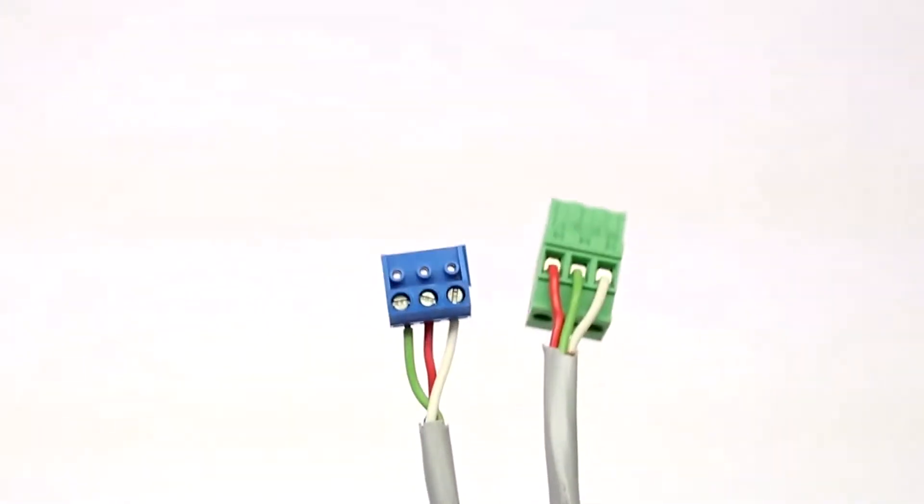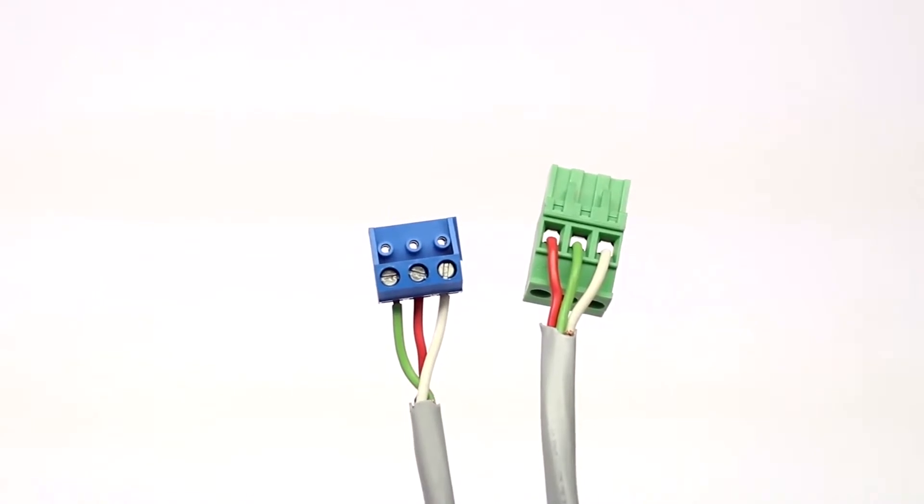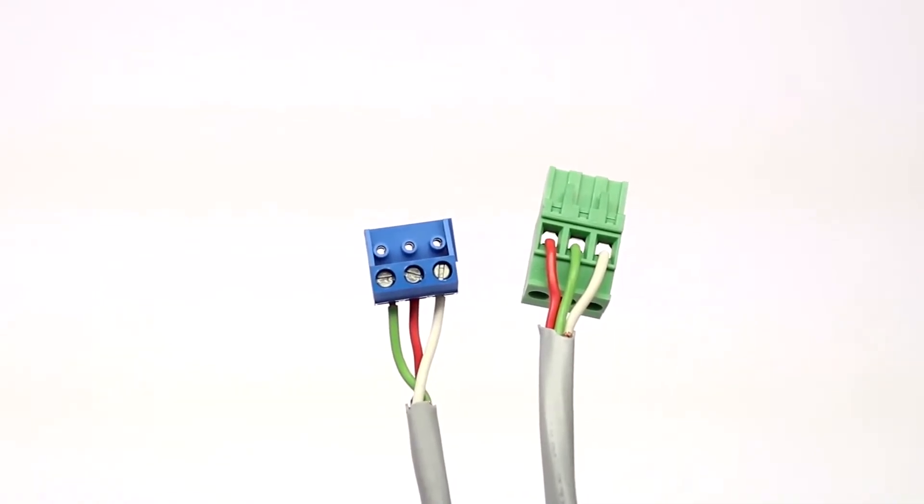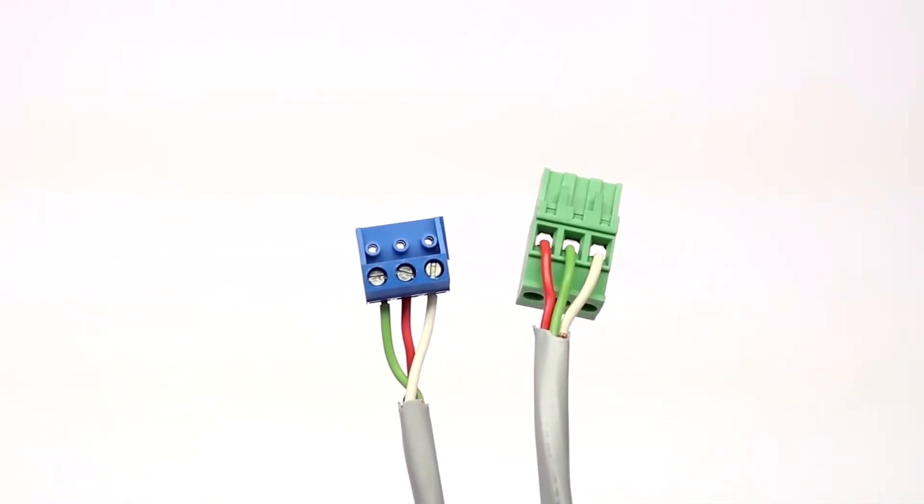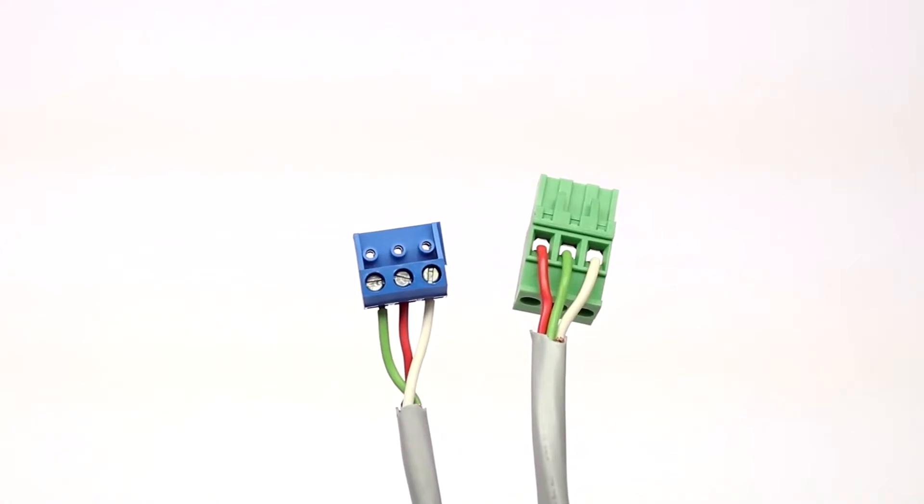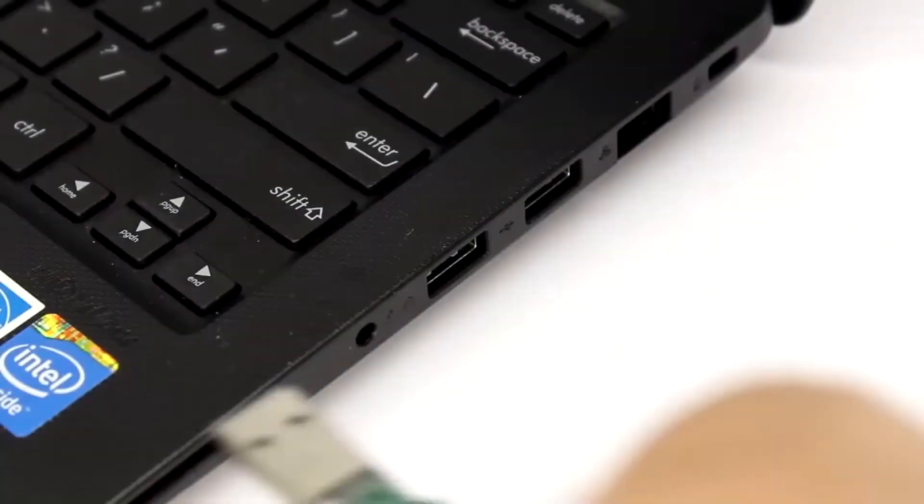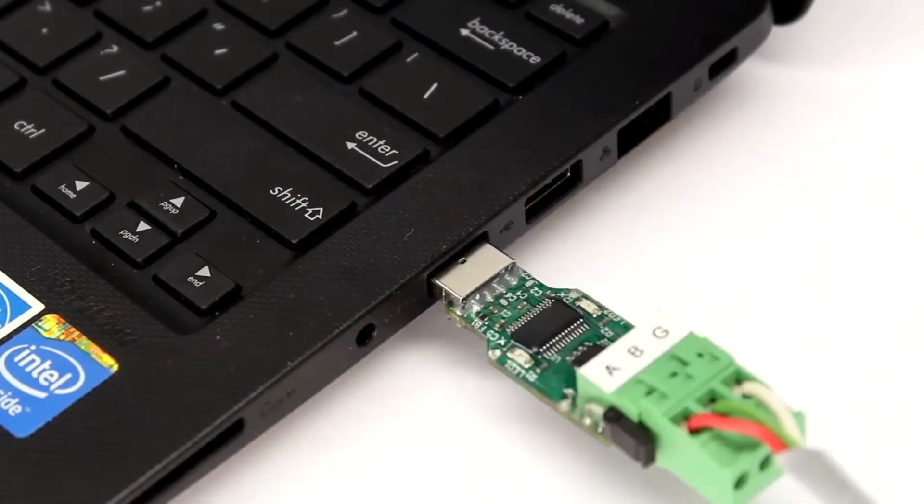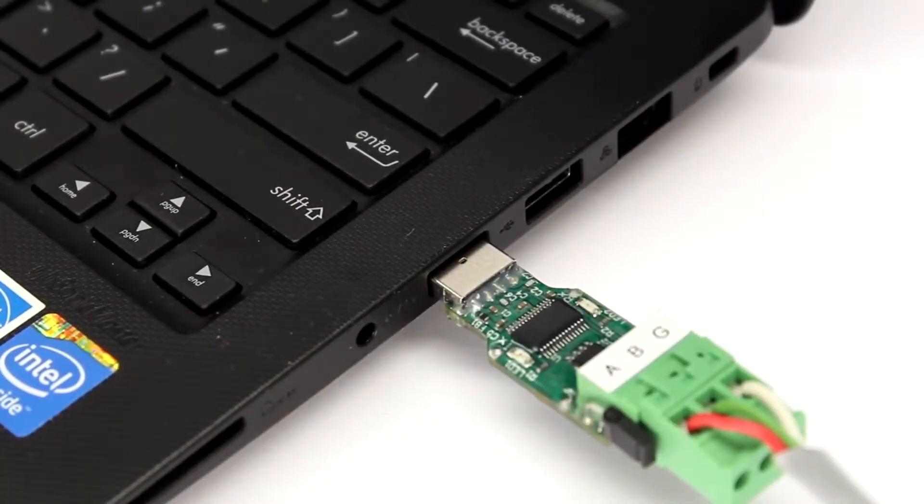Using this wiring diagram, connect the CA 702 to either three pin terminal block at TB6 or TB7. You may use any multi-conductor cable for this short programming cable. Connect the CA 702 to an open USB port on a laptop that can be carried to each door controller.